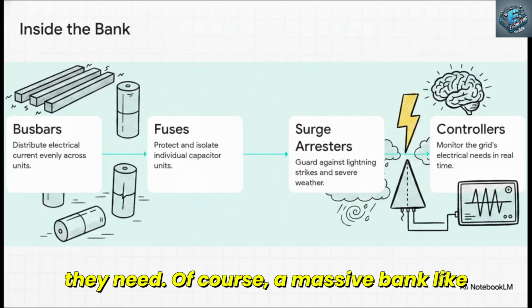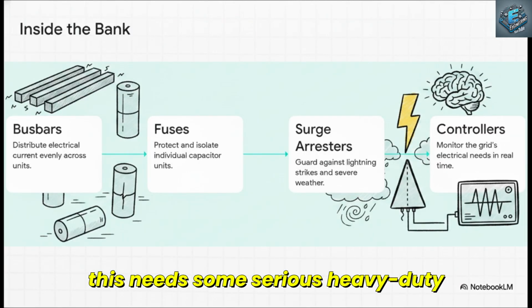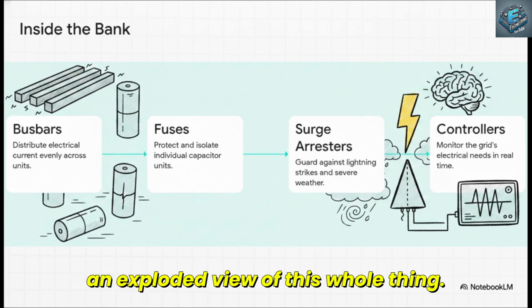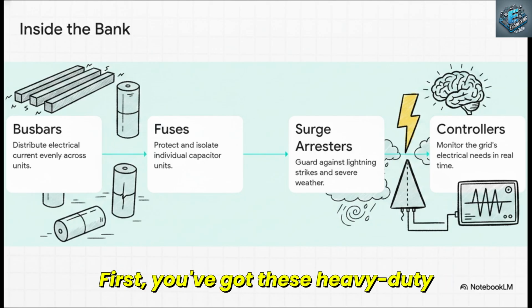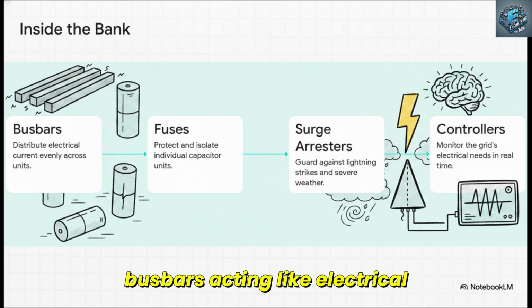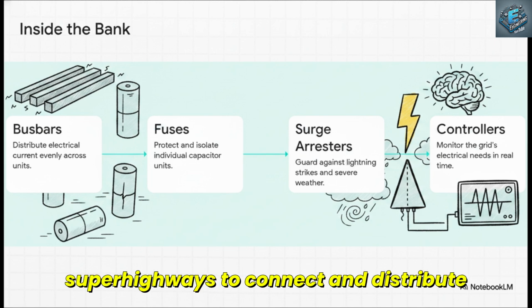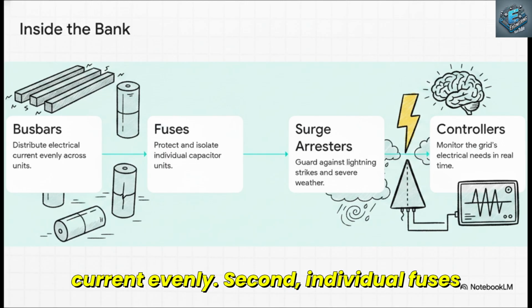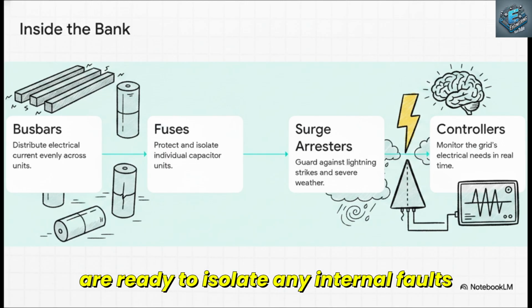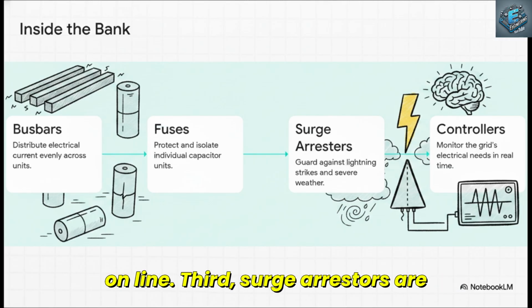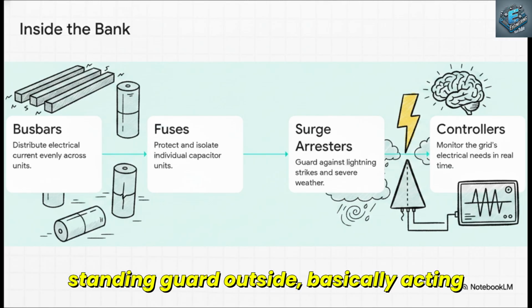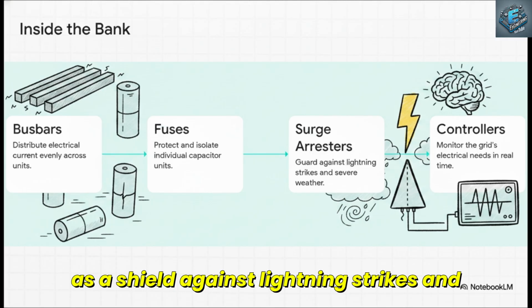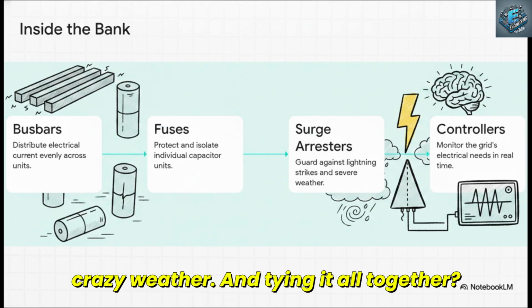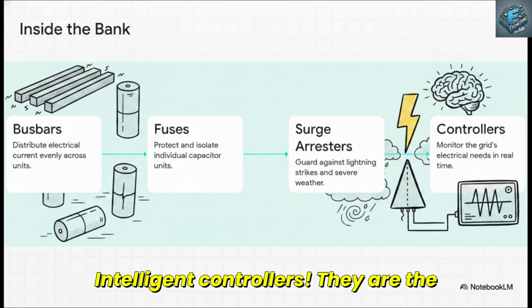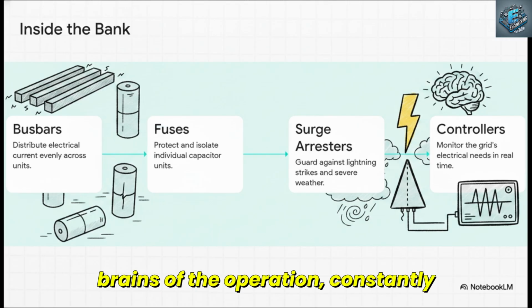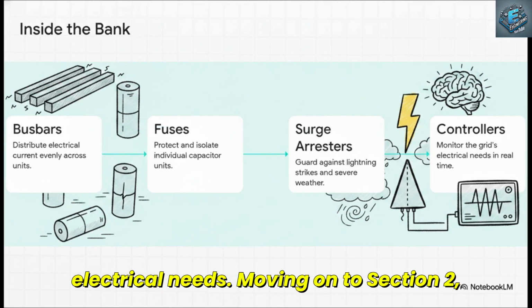Of course, a massive bank like this needs some serious heavy-duty support components to run safely. Picture an exploded view of this whole thing. First, you've got these heavy-duty bus bars acting like electrical superhighways to connect and distribute current evenly. Second, individual fuses are ready to isolate any internal faults so the rest of the bank can actually stay online. Third, surge arresters are standing guard outside, basically acting as a shield against lightning strikes and crazy weather. And tying it all together? Intelligent controllers. They are the brains of the operation, constantly monitoring the grid's real-time electrical needs.